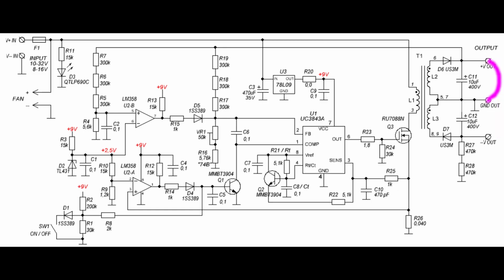However, if only the first output is used, the voltage on the second part would fluctuate out of control, very likely significantly exceeding -400 volts. Unfortunately, this would put the corresponding filter capacitor in a condition of severe stress because it is rated only for 400 volts.